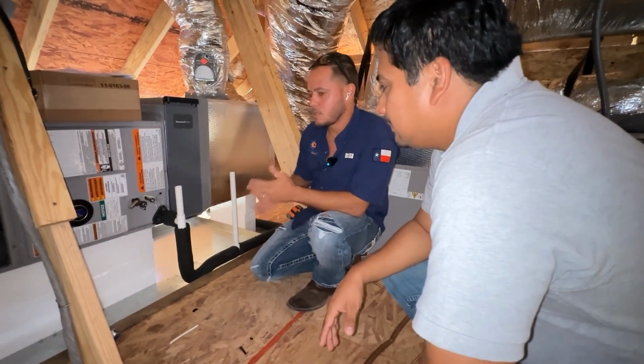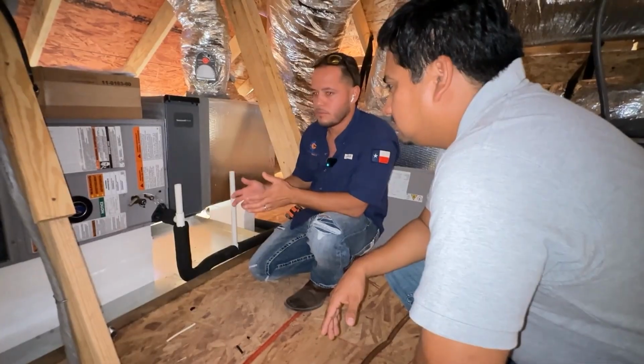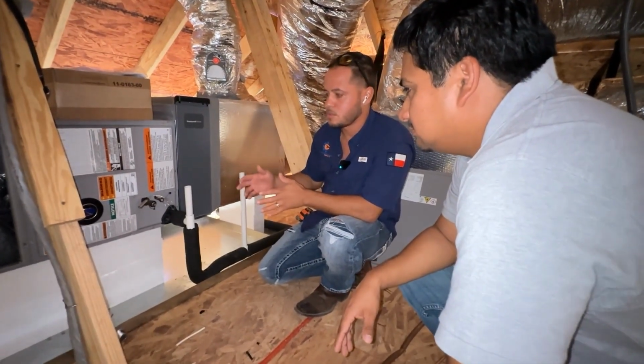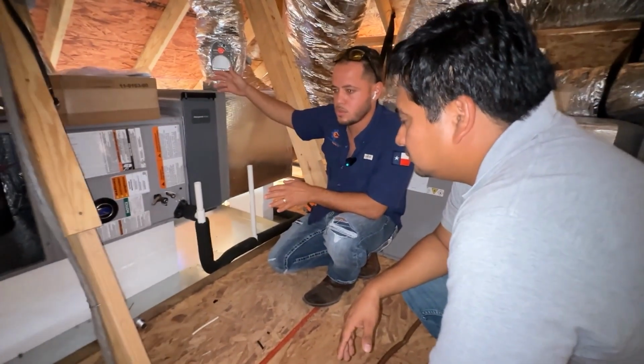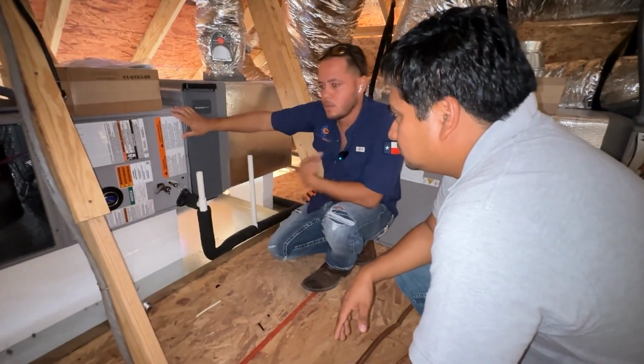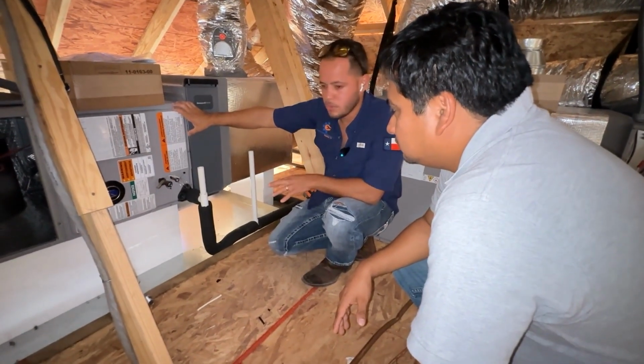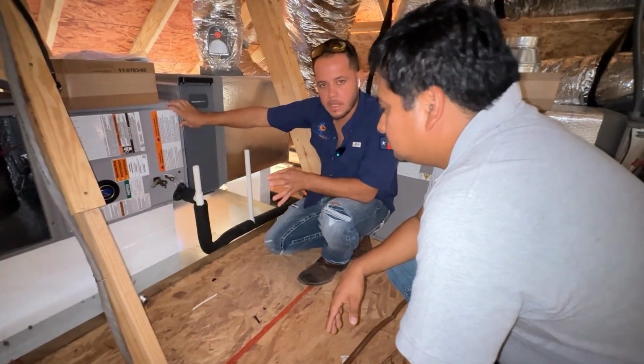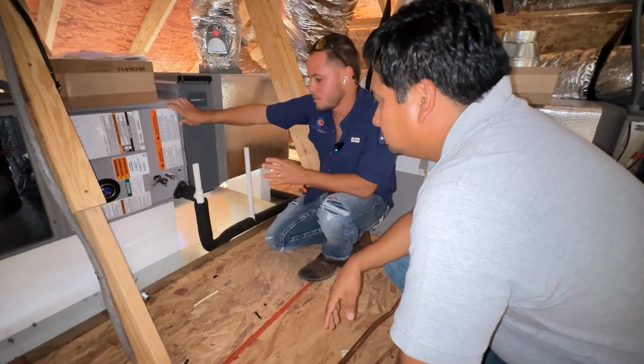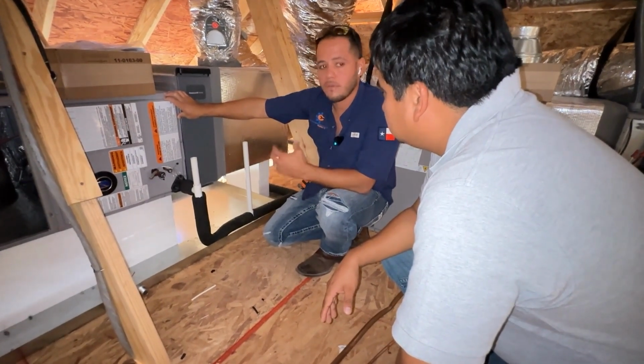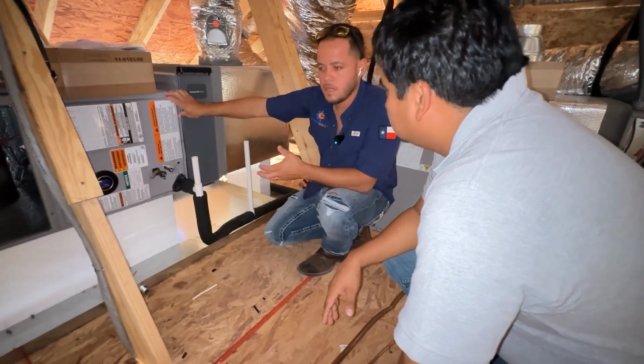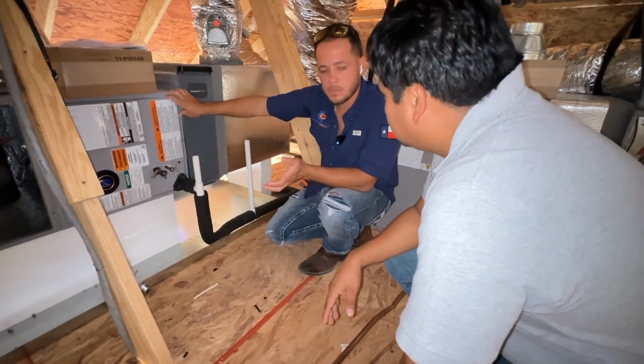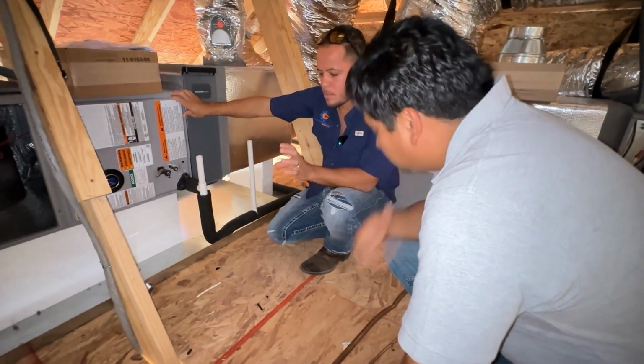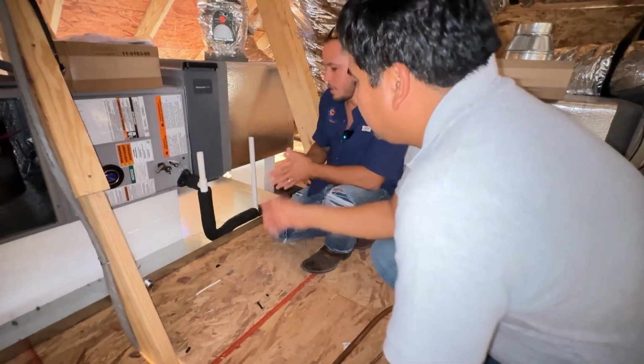There are a lot of different ways that people wire the float switch. Sometimes they wire it so that just the outside condenser will stop, but this one will keep running. The way we like to do it is we connect the float switch directly to the thermostat. So whenever the float switch has water, it cuts the power of the thermostat, and then you have a problem. It doesn't matter if you put batteries in the thermostat or whatnot. The thermostat might come on, but the system will not. Okay, cool.